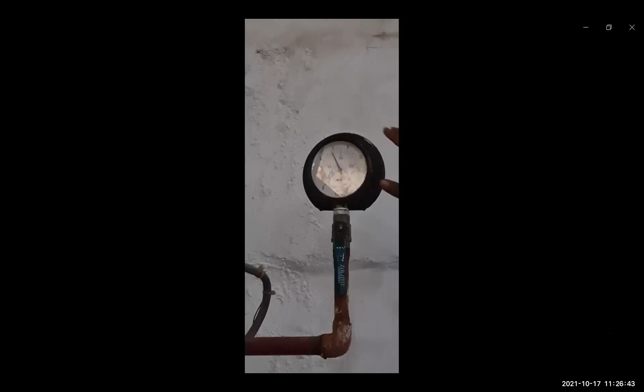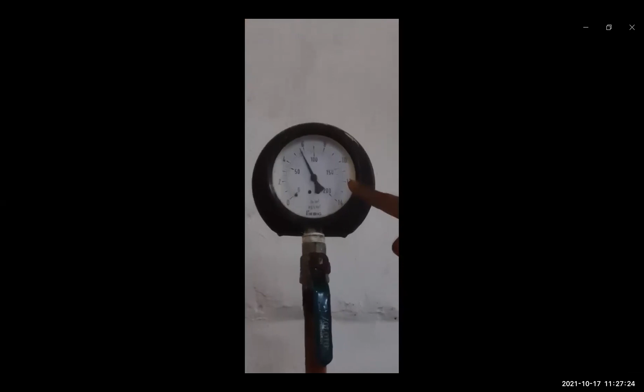Once it decreases and reaches 4 kg, these pumps will automatically start operating. This we call the cutoff range of the pump. So we'll demonstrate how it works. Right now somebody is using the water line point. We can treat this as a fire alarm. You can see this 6 kg is going down. If there is a fire and the sprinkler starts, this pressure starts going down because water is getting discharged from those lines, right? So this pressure will keep coming down.